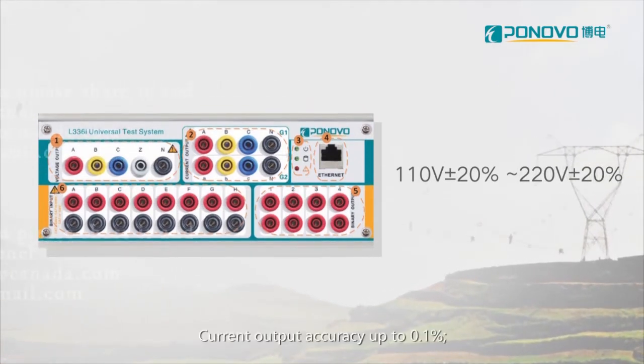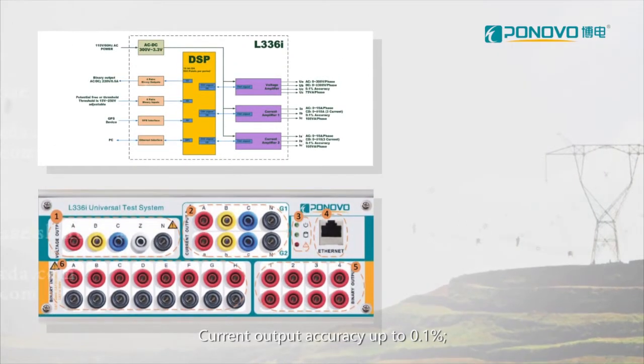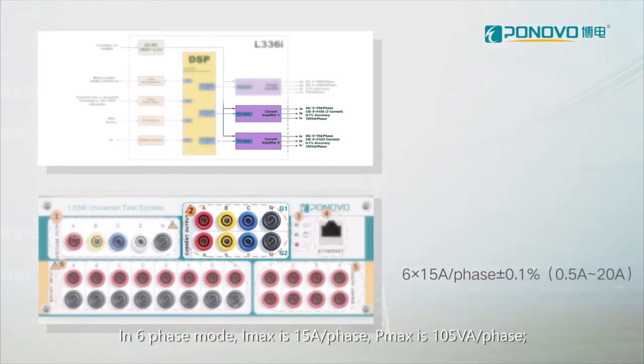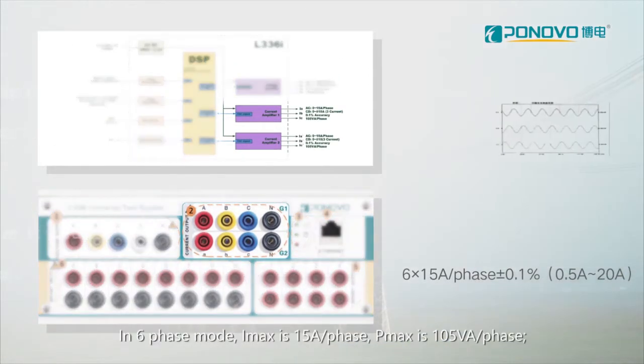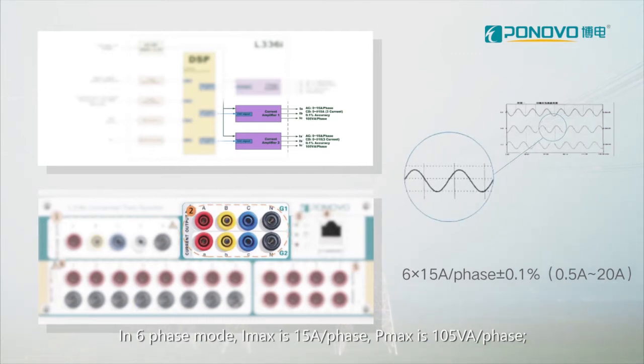Current output accuracy up to 0.1 percent. In six-phase mode, IMAX is 15 Ampere per phase. PMAX is 105 VA per phase.